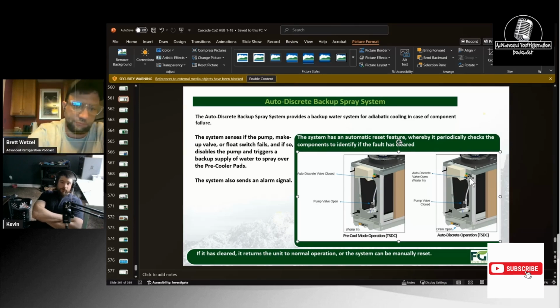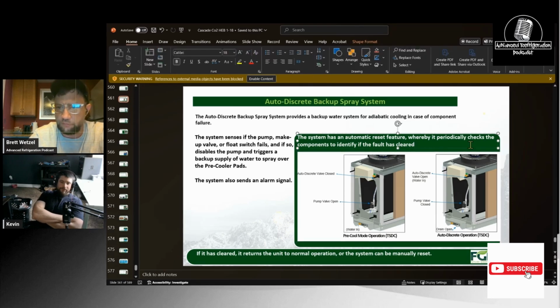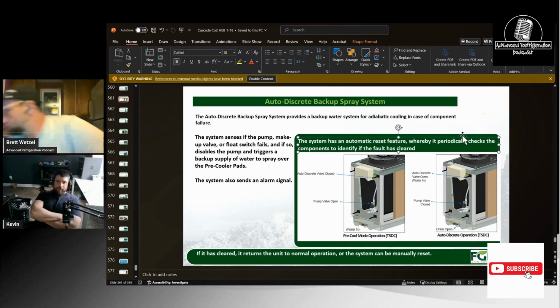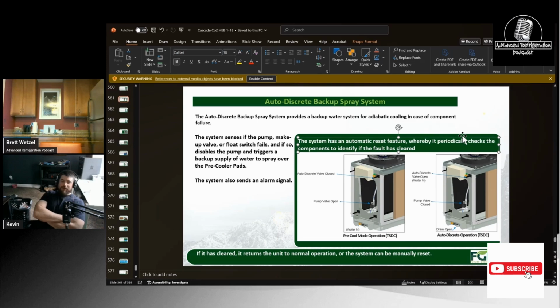Yeah, and it works pretty good. It's a great backup, as long as there's a hose bib close on the roof. Usually there is, right? I haven't seen it on a lot of stores. I know Target is pretty good about it, but I've been making the plumber install a hose bib on the water feed line. I give him the hose bib pieces, and that way he can put it in, because it only benefits us to have a hose there. Then I leave a 25-foot hose on the roof with a garden hose connection. There's no reason anybody shouldn't be cleaning the gas cooler at that point if there's already a hose up there. That was a great thing about Aldi when they started putting all the hose connections right next to the rack. You leave a 25-foot hose up there, and you could easily clean everything.